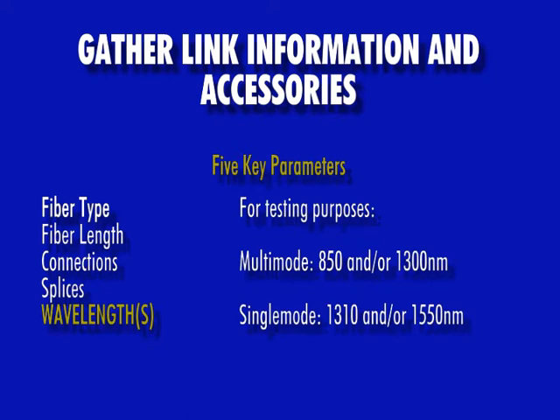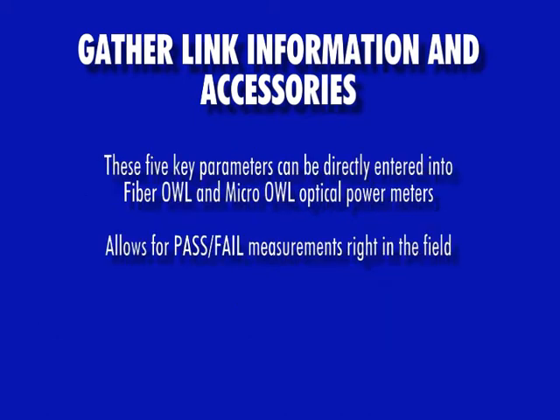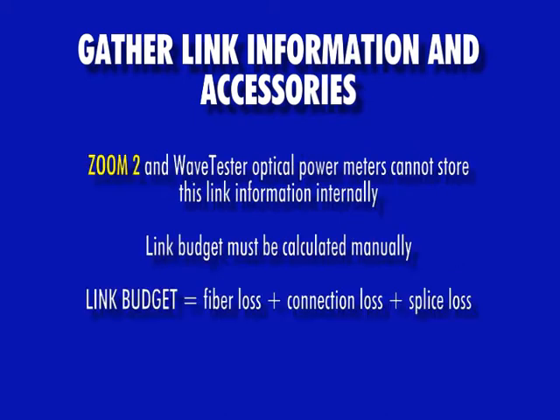Lastly, the user must determine what wavelengths they will test at. For multimode, this is 850 and/or 1300 nanometers. For single mode, this is 1310 and/or 1550 nanometers. When using a Micro OWL or Fiber OWL optical power meter, these parameters can be entered directly into the device to calculate the link budget. However, if the link budget needs to be calculated manually, this is done by adding together the fiber loss, connection loss, and splice loss.